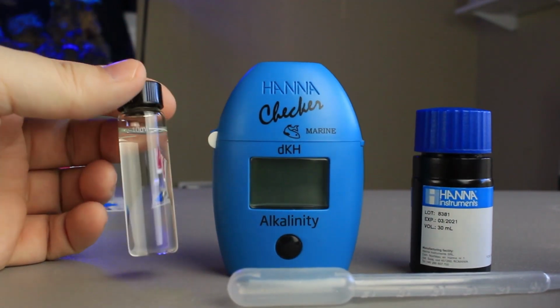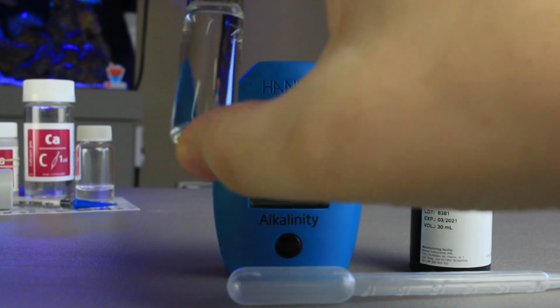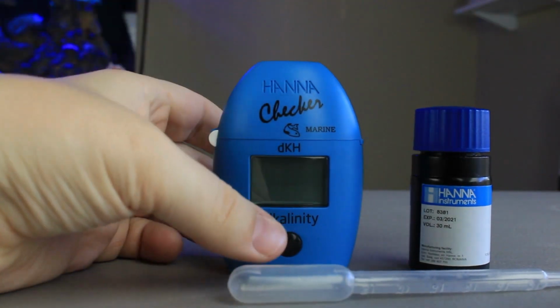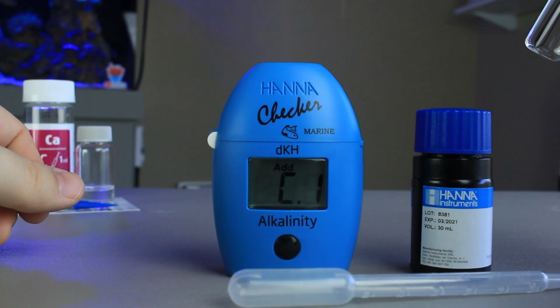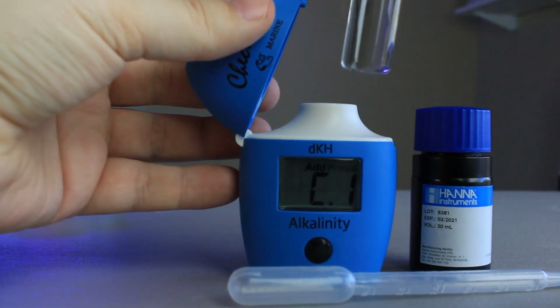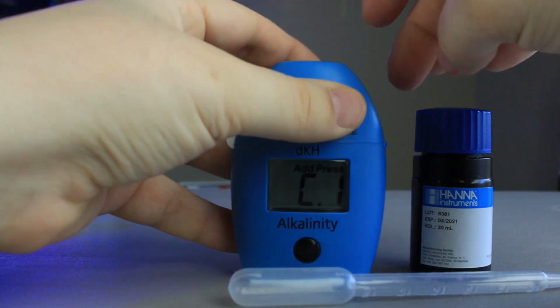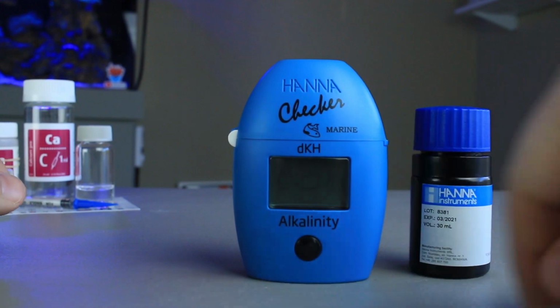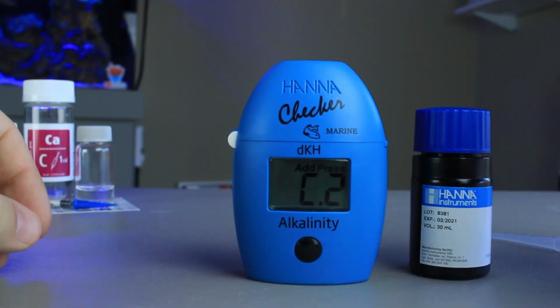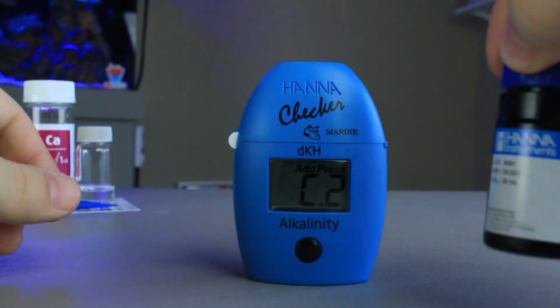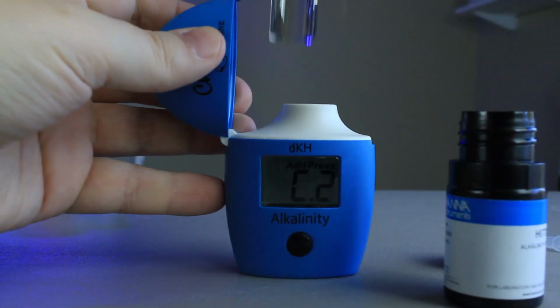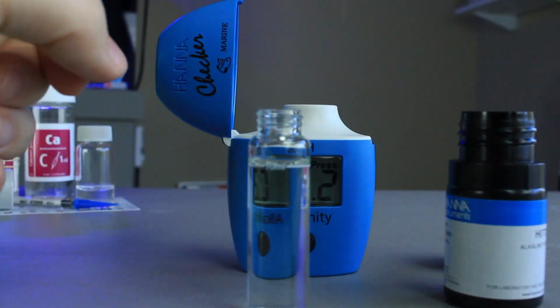So now that we have our sample water from our tank, we're going to make sure that the vial is clean using our microfiber cloth here. Turn on the Hanna alkalinity checker. When it says C1, your sample is ready to be placed in the tester. We're going to hit the button here. Okay, now when it says C2, I like to shake up the reagent just a little bit. Pull the sample out of the tester. And we're going to put 1 ml of reagent into the test vial here.